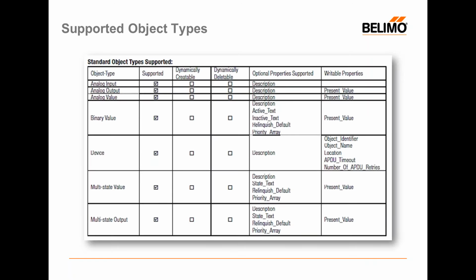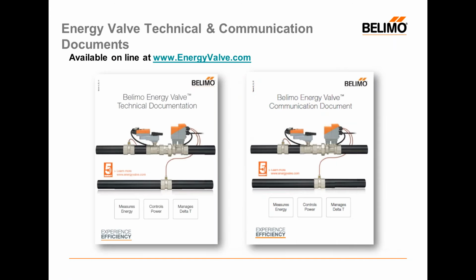It supports standard object types: analog inputs, outputs, values, binary values, multi-state values and outputs, all the standard objects that are associated with the BACnet application-specific controller. And if you need any more detailed information on the functionality and setup of the energy valve, you can reference the BELIMO energy valve technical documentation that you see here on the left.